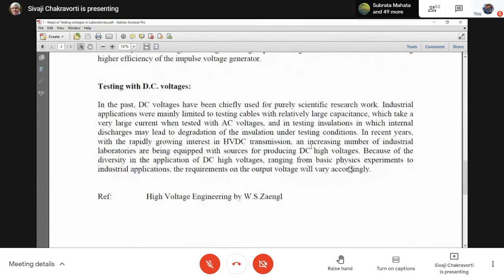And finally, DC voltage. Now, these DC voltages are coming into the picture again because HVDC lines are now very common, and there we have a lot of equipment which we use, and therefore they cannot be tested under AC voltages. They have to be tested under DC voltages, and therefore we need DC voltage generation in the lab also. And DC voltages are also required in some of the fundamental experiments, breakdown experiments and others. So primarily, these are the three types that we'll discuss from the generation side.